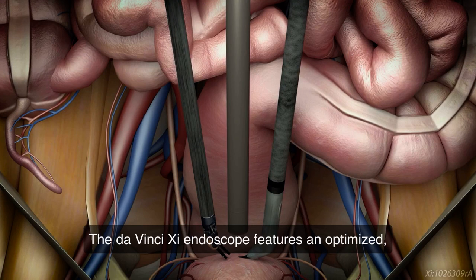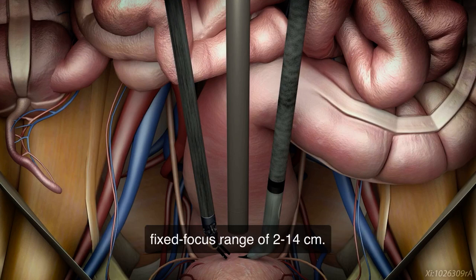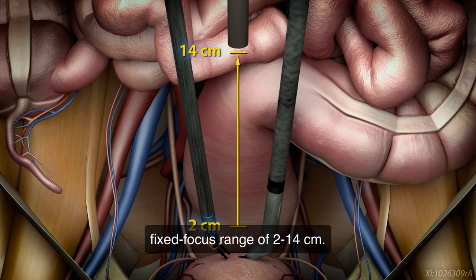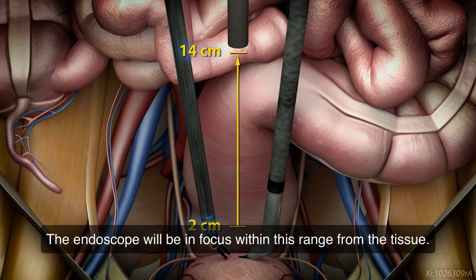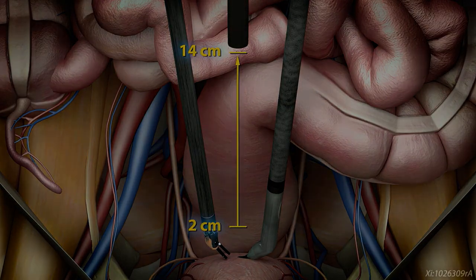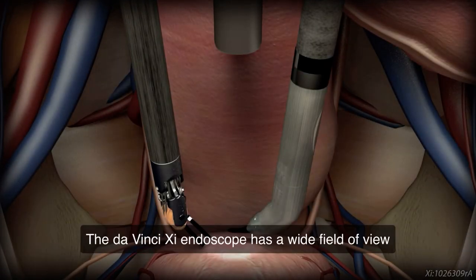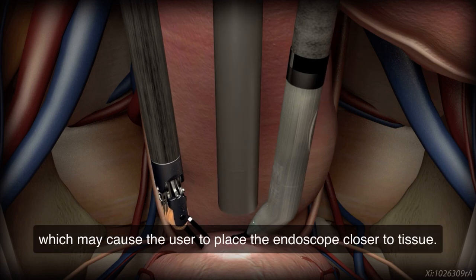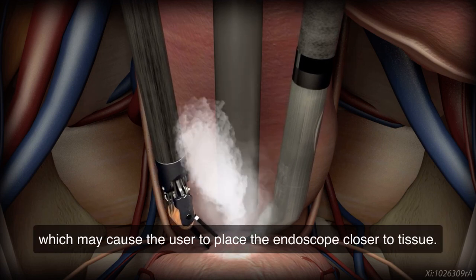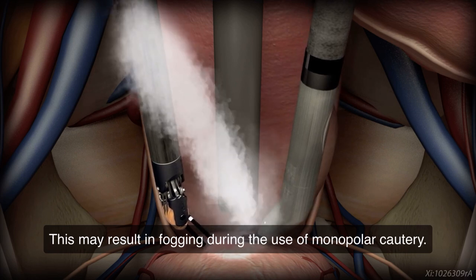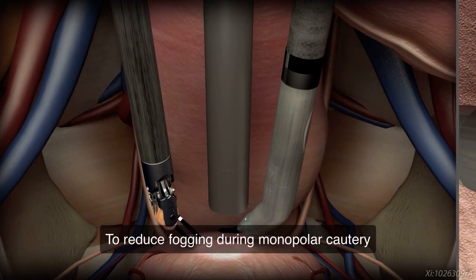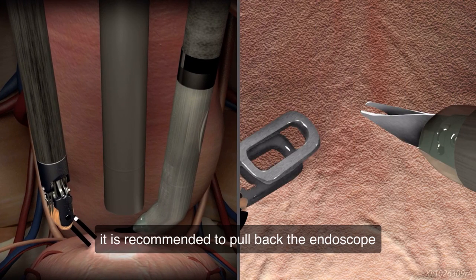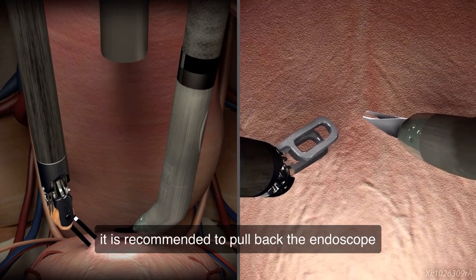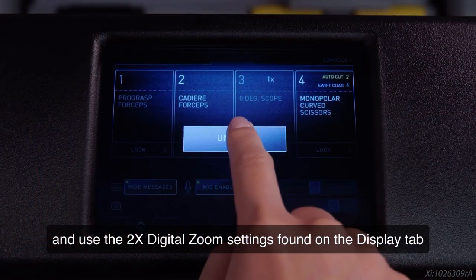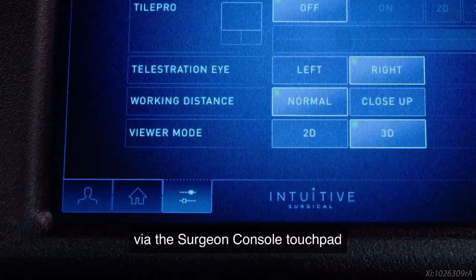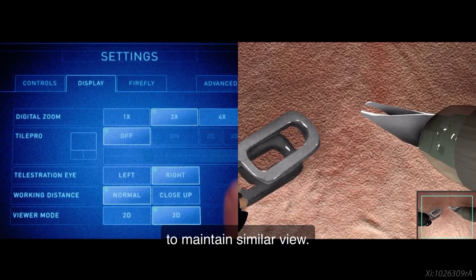The da Vinci Xi endoscope features an optimized fixed focus range of 2 to 14 centimeters. The endoscope will be in focus within this range from the tissue. The da Vinci Xi endoscope has a wide field of view which may cause the user to place the endoscope closer to tissue. This may result in fogging during the use of monopolar cautery. To reduce fogging during monopolar cautery, it is recommended to pull back the endoscope and use the 2x digital zoom settings found on the display tab via the surgeon console touchpad to maintain a similar view.